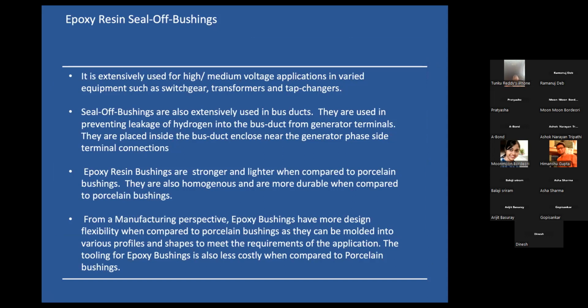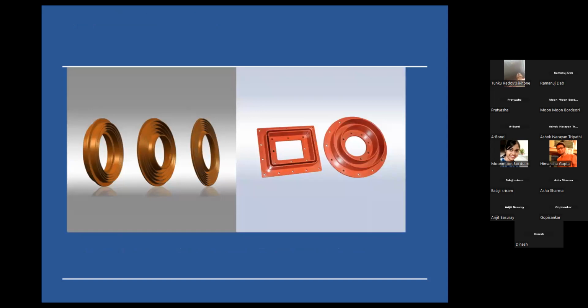from the generator terminals. Now, when compared to porcelain bushings, epoxy resin bushings are much stronger and much lighter in weight. They're also more durable. Specifically from a manufacturing perspective, they have more design flexibility because they can be molded into various profiles and shapes, which is not possible with porcelain bushings. And the tooling we use for epoxy bushings is also much lower in cost compared to porcelain bushings. It's just a slight 3D profile of our epoxy bushings.